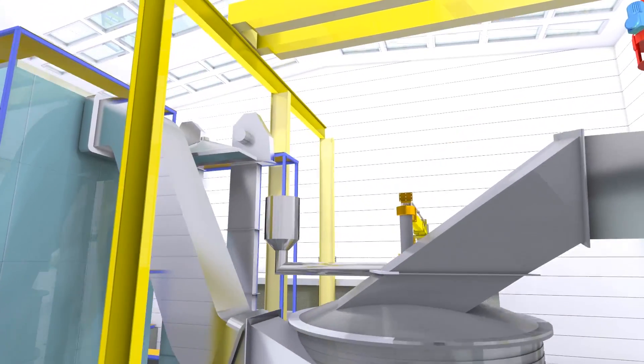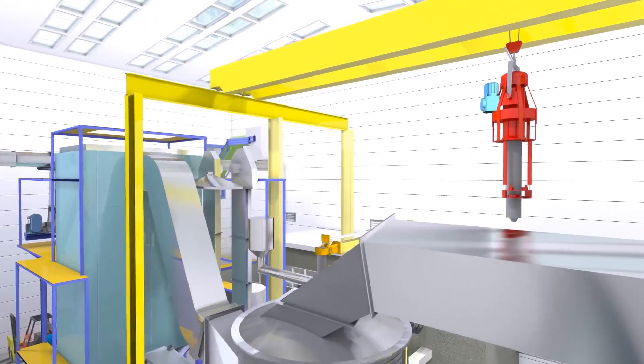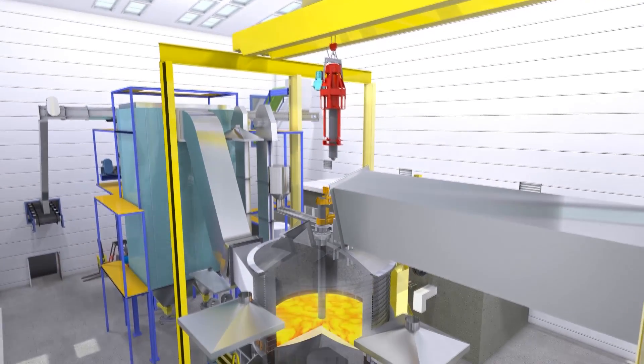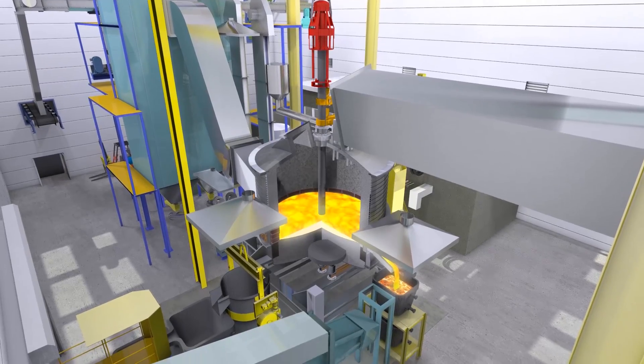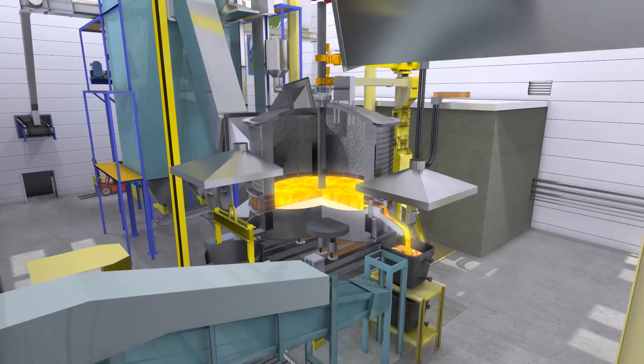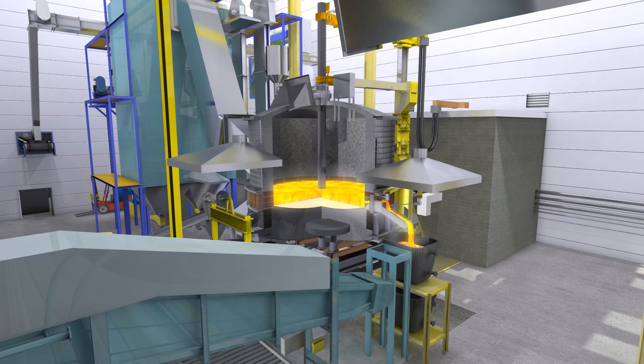The plasma arc in the converter produces a very high temperature and emits intense ultraviolet light that both fully cracks the remaining long-chain hydrocarbons to produce a very clean syngas, and vitrifies the inorganic bed material, which is continually drawn off in a molten state, known as plasma rock. Plasma rock is mechanically strong, environmentally stable, and approved by the Environment Agency as a secondary aggregate product.